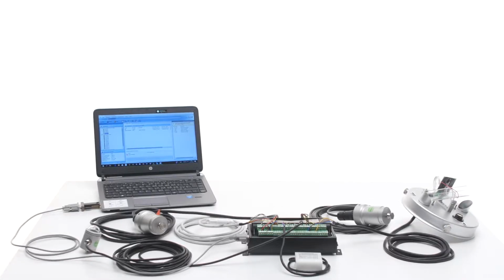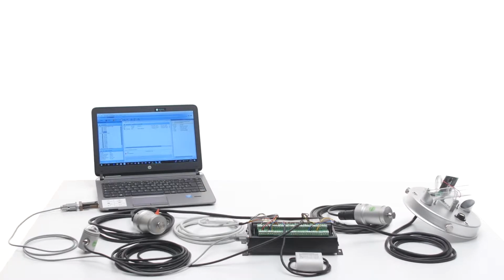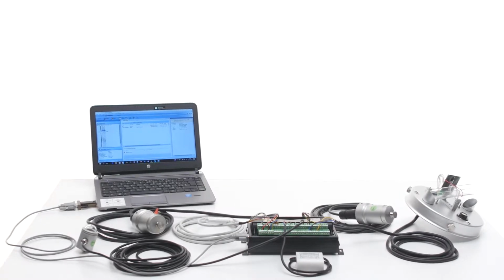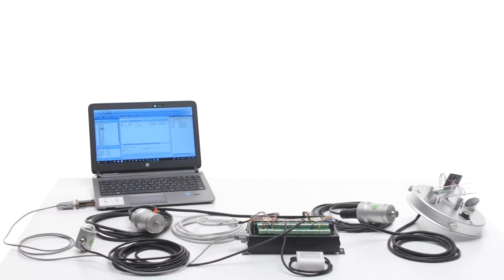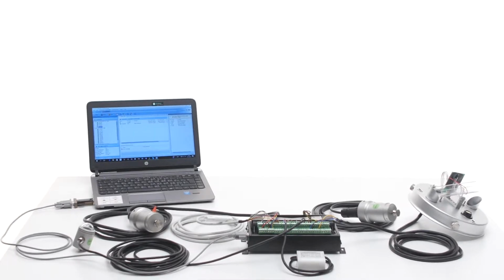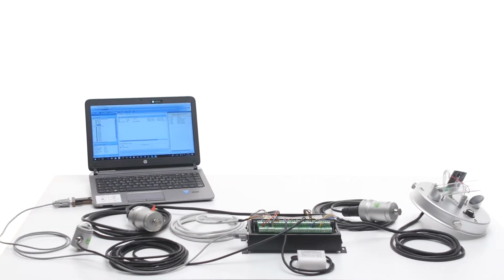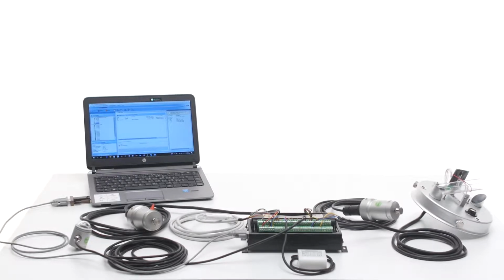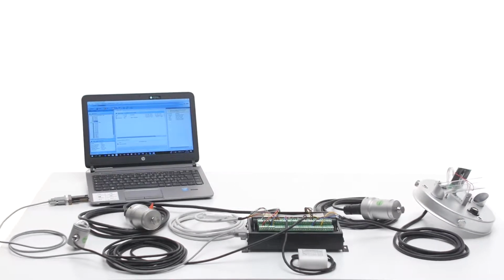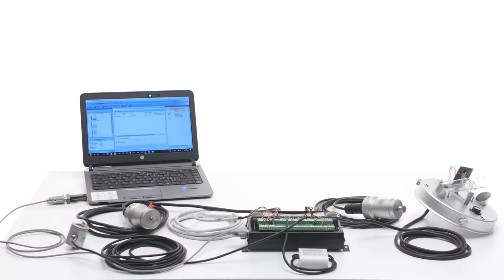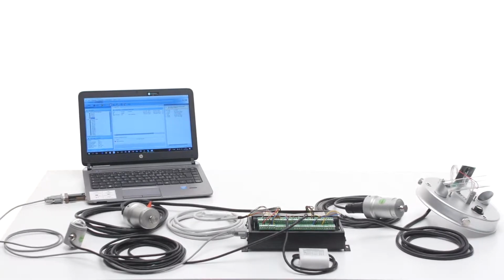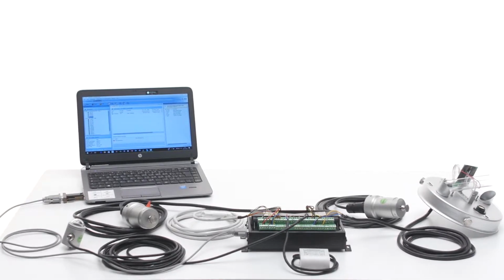Before starting the on-site installation, it is advisable to make a preliminary functional test in the laboratory, where you become familiar with the system, check its operation and configuration. To carry on with the test, it is required to connect the sensors to the data logger and verify their measurements using 3DOM software, supplied inside the pen drive, which should be installed before.